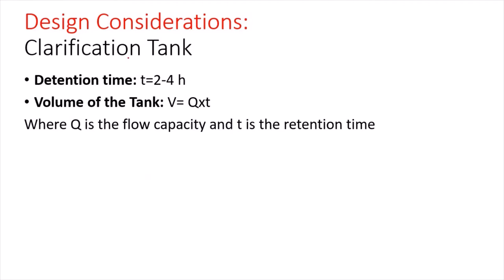For the clarification tank, the detention time is between 2 to 4 hours so that the flocs can have enough time to settle down. The volume of the tank is V equals Q times t. And here also Q is the flow capacity and t is the retention time.